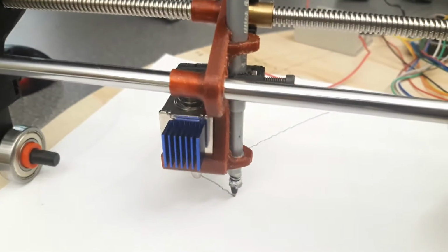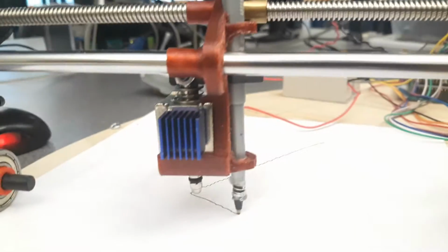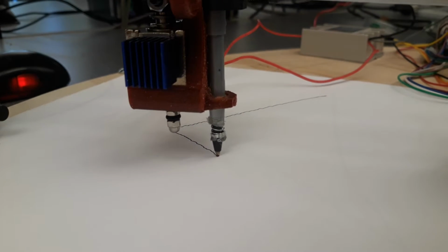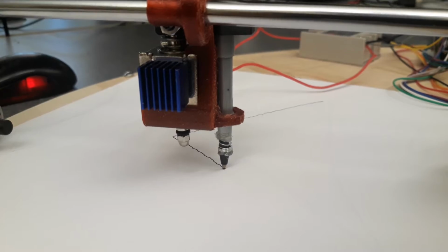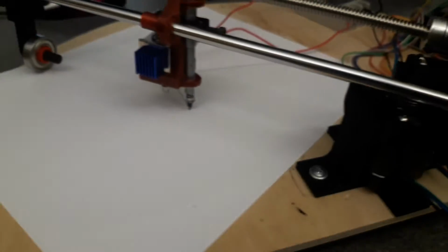There's also a pen actuator here that I talked about a little while ago, and that uses a solenoid, and when it's activated it forces the pen down. The pen has been modified to have a spring on the end. This is just to ensure that consistent pressure is applied to the paper even with inconsistent board flatness as it's drawing.